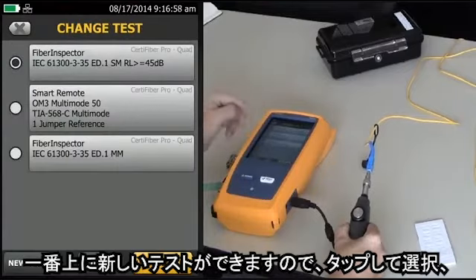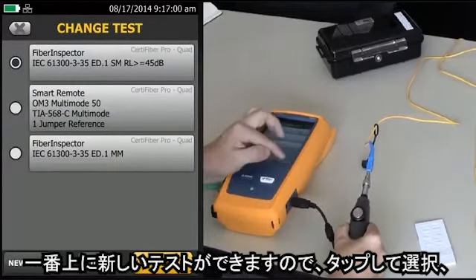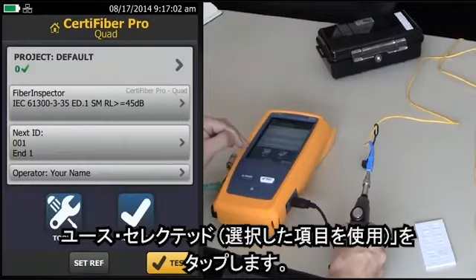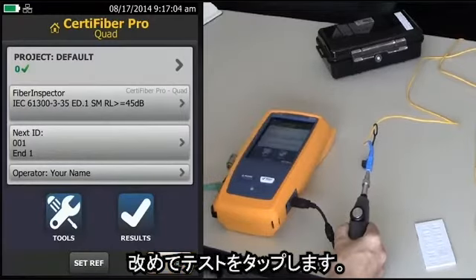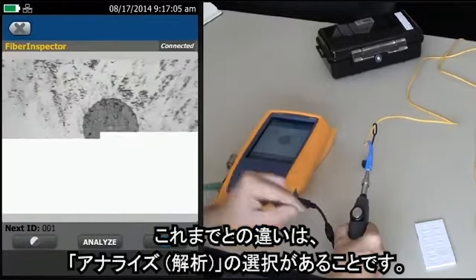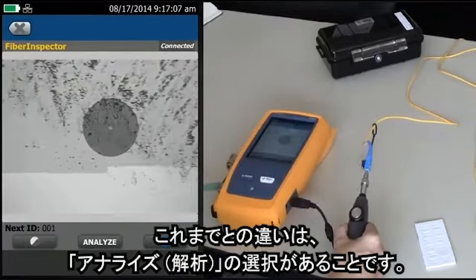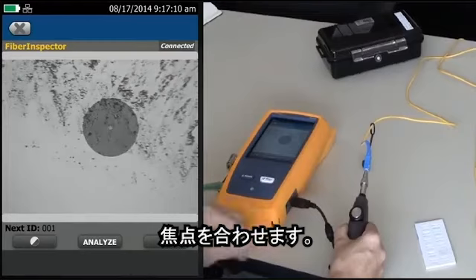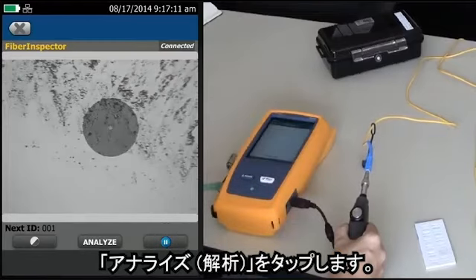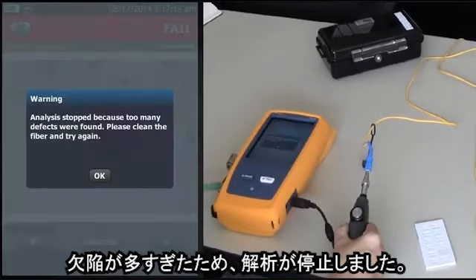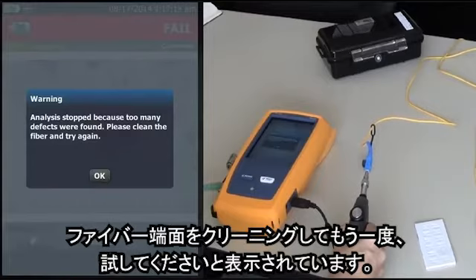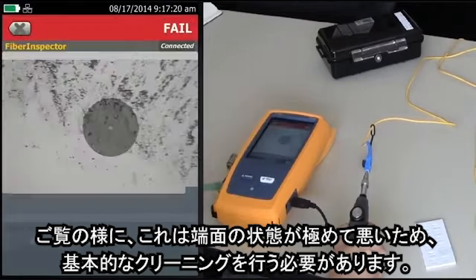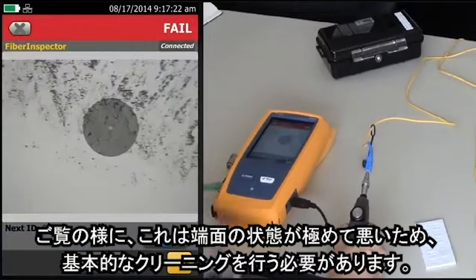Here's my new test at the top here, so I'm going to highlight it, use selected, and if I hit test now, the difference this time is you'll see the analyze option. And if I get that focused in, now if I tap analyze, analyze stopped because too many defects were found. Please clean the fiber and try again. This, as you can see, is just so bad, we need to do some basic cleaning.